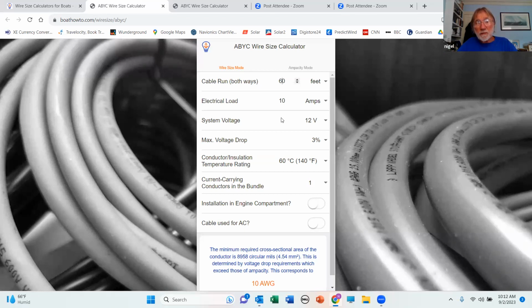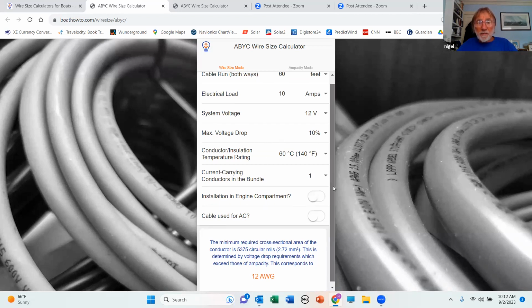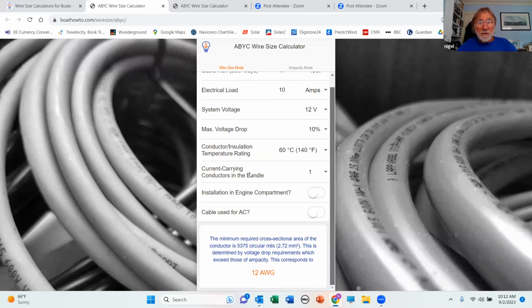And then we're going to put the system voltage in. Most of you have 12 volts. I actually have 24 and 48 volts on my boat, so I have three different voltages. And then we're going to put the maximum voltage drop in. In this case, we'll go for 10% because we're going for the minimum standard. And now we're going to put the conductor insulation temperature rating in here. I'm going to leave that at 60 C for the minute, which is the lowest rating you're likely to find on conductors, because some European boats use 60 C conductor. Mostly in the States, we never do.